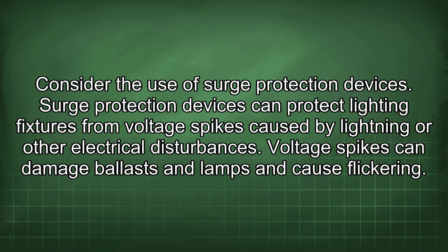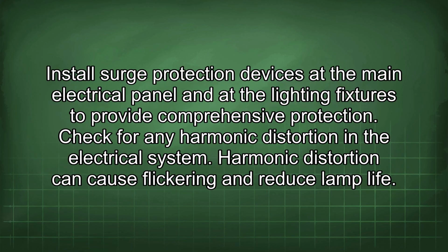Consider the use of surge protection devices. Surge protection devices can protect lighting fixtures from voltage spikes caused by lightning or other electrical disturbances. Voltage spikes can damage ballasts and lamps and cause flickering. Install surge protection devices at the main electrical panel and at the lighting fixtures to provide comprehensive protection.